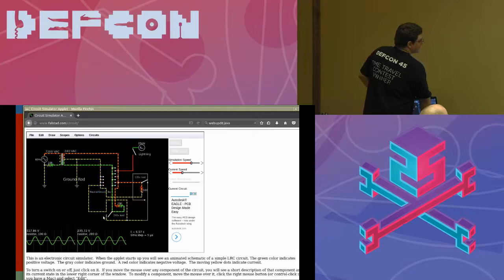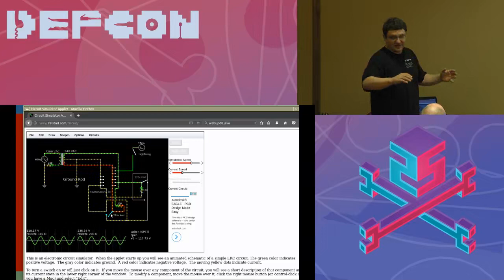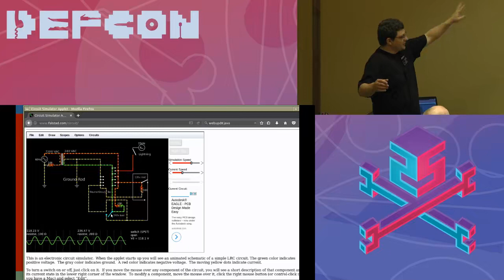Because that fault is completely contained within your house's transformer. That neutral ground bar, where your grounds come together with the neutral, is where you're short-circuiting. So if you have a washing machine with a metal chassis, and a hot wire comes unattached and touches the chassis, it's a short circuit through the neutral ground bar, through the transformer in your house — nothing to do with the ground rod. So what does the ground rod actually do?